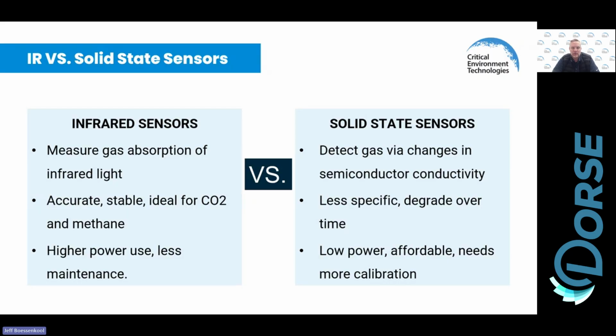And then calibration frequency, right? Sensors should be calibrated regularly, and our recommendation is every 6 to 12 months. That's going to depend on the type of sensor as well. Your standard sensor every 12 months, oxygen sensors every 6 months, and like I said, infrared sensors can be every 12 months, or sorry, every 2 years.